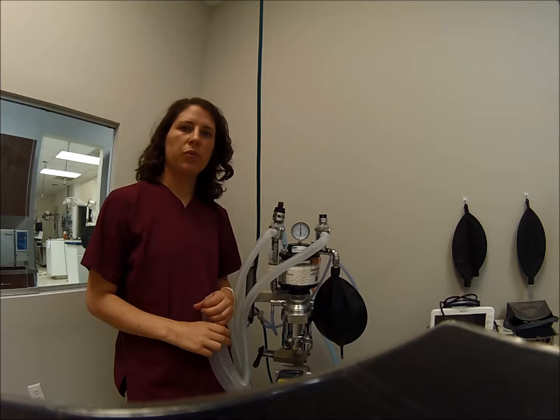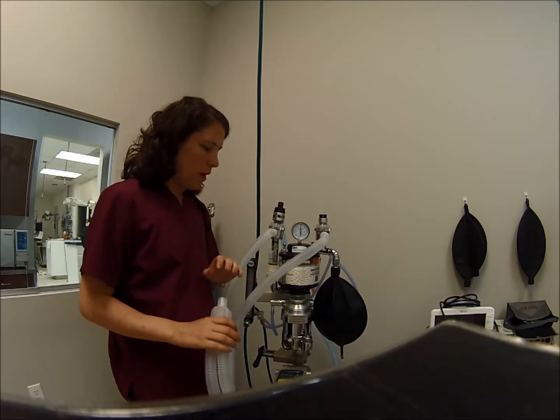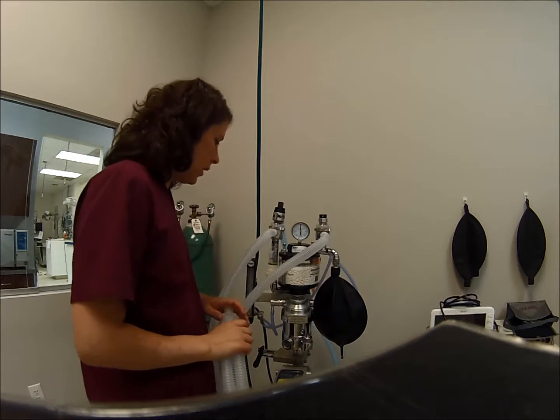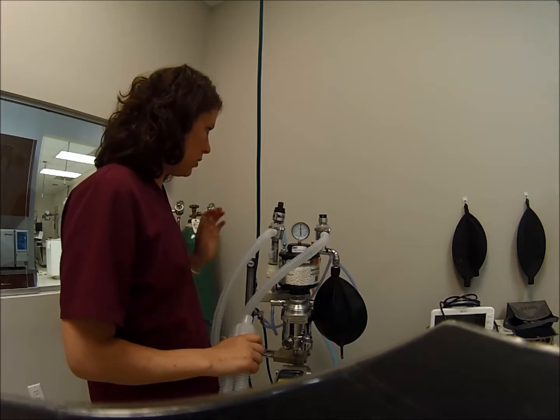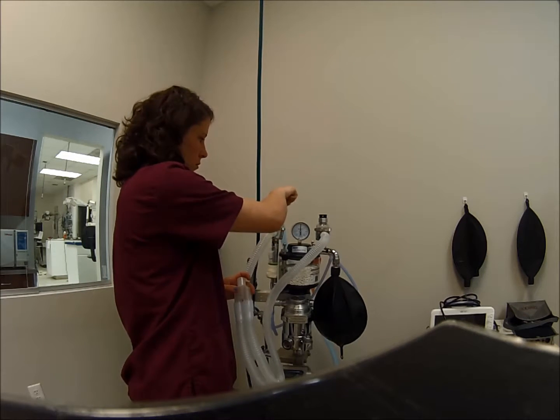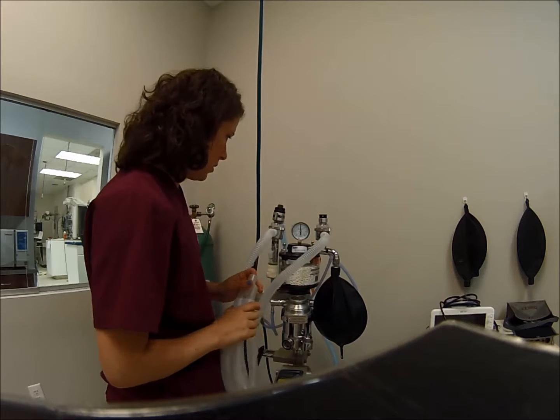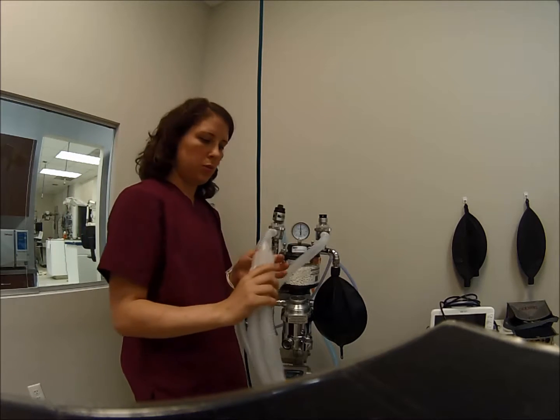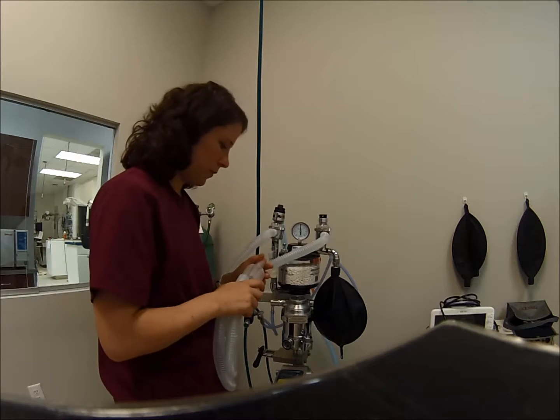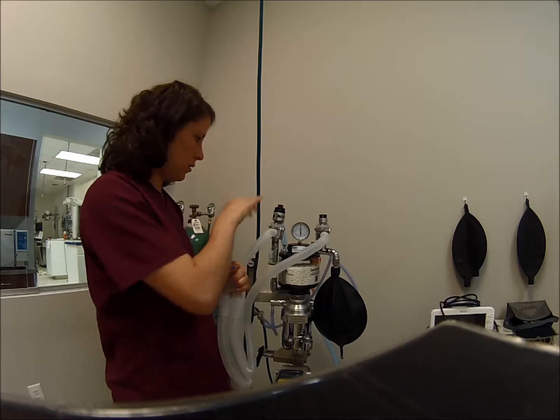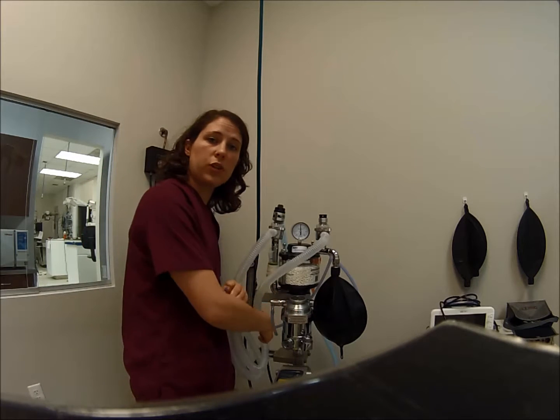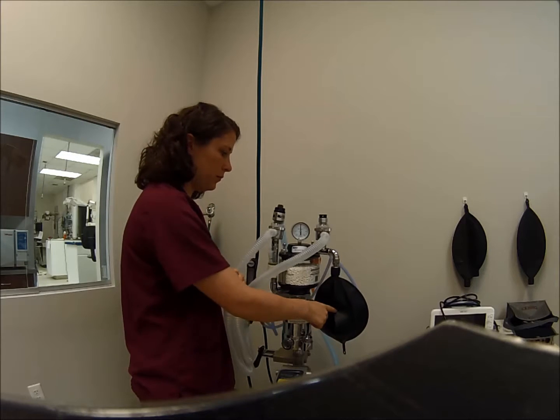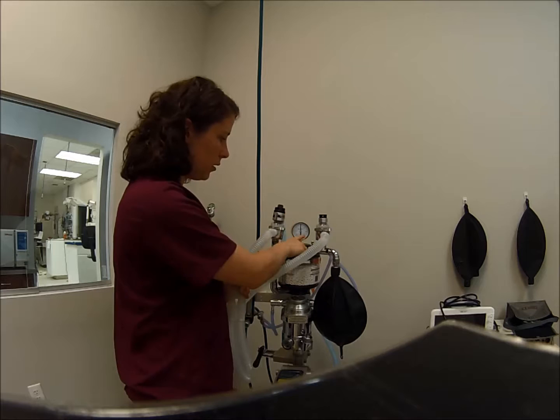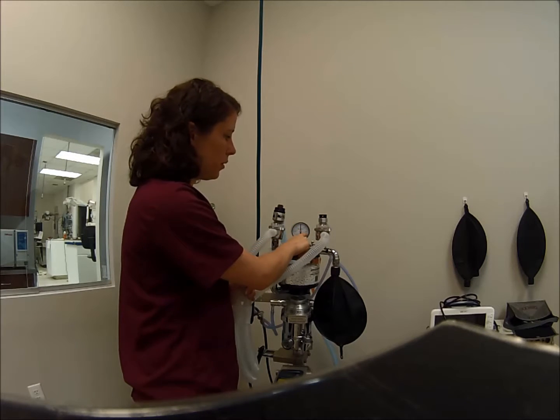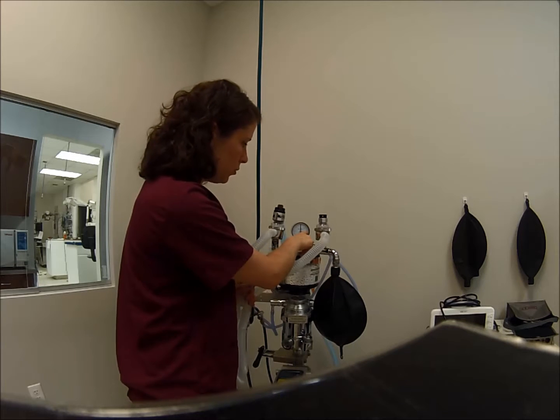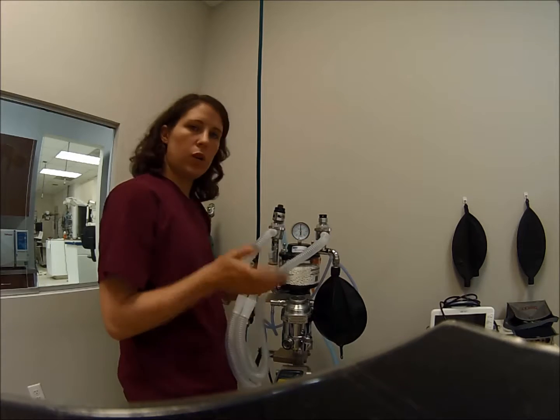I'm going to be demonstrating how to perform a leak test on the anesthesia machine. I have my rebreathing circuit hooked up, and first thing I'm going to do is close my pop-off valve. Now I'm going to plug the other end of my Y-piece tubing with my hand. Make sure no oxygen will escape from either end of the circuit. I'm going to use the fast flush valve to quickly infuse oxygen into my bag and see if my needle on the manometer starts to descend. I'm going to inflate the bag till I get to the 40 centimeters H2O and watch my needle from there.